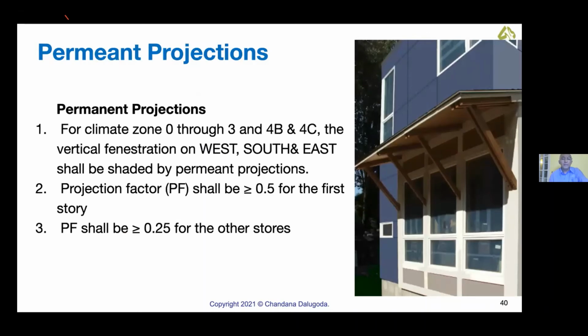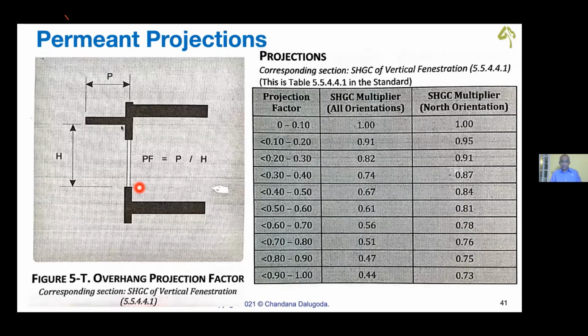Next thing, for fenestration, it is suggested to have permanent projections, especially on the west, south and east sides. Projection factor shall be 0.5 or larger. Now, what is projection factor? It is the awning width divided by the height of the projection from the sill level. You can see when the projection factor becomes higher and higher, your SHGC, that is the solar heat gain coefficient multiplier, becomes smaller and smaller. So your heat transfer reduces.